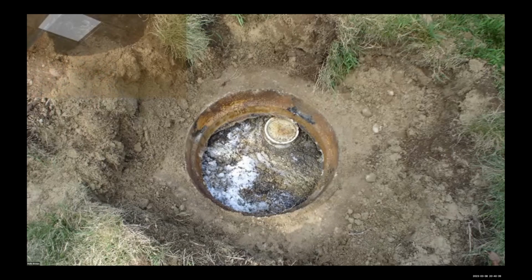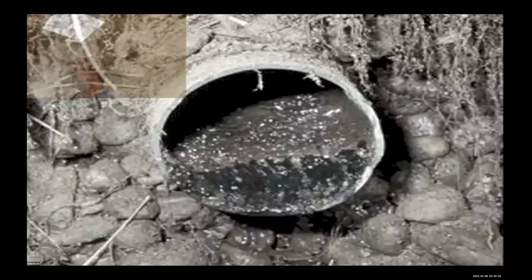So anytime that we can't see where the water goes out, it's overfull. It's really hard to explain to a homeowner what's overfull. They look in a tank, they see water level 12 inches down, like, holy cow, it's full. Well, it's full, but then it overflows, right? Overfull is a problem. That means it's clogging the back line, your absorption system isn't absorbing as fast as it's using.